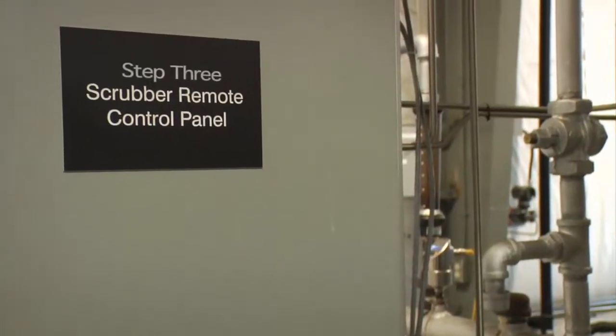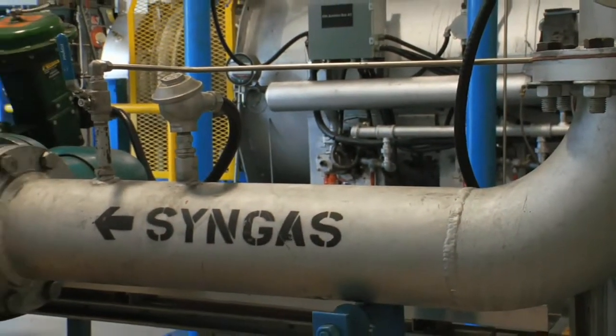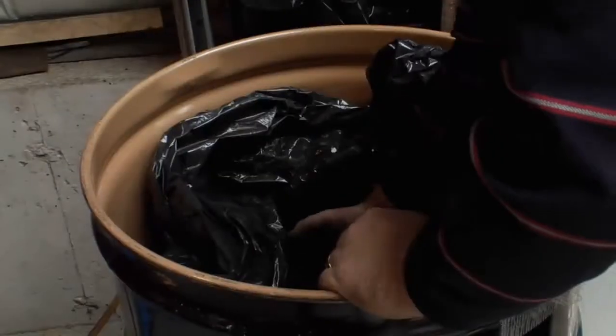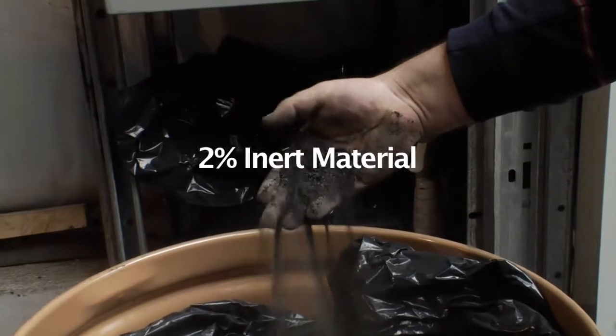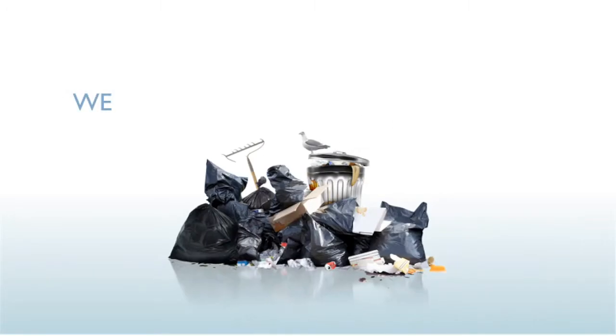The syngas is drawn out of our kiln by two large syngas blowers, which transport the gas from the kiln through a scrubber and a HEPA plus carbon sorbent bed filter system. This gas cleaning system neutralizes any acids and, combined with the filter system, removes any particulate and other metal vapors. The byproduct of our system is 2% inert material composed primarily of minerals and non-ferrous metals that are not reformed by the process — this inert material can be used as a filler for asphalt or concrete. The gas is now clean and ready to be used as a green fuel source in any application where natural gas may be used, including the production of electricity.